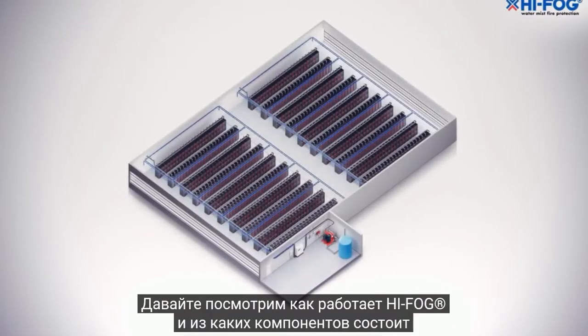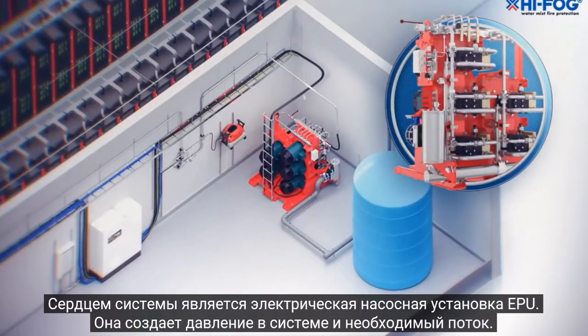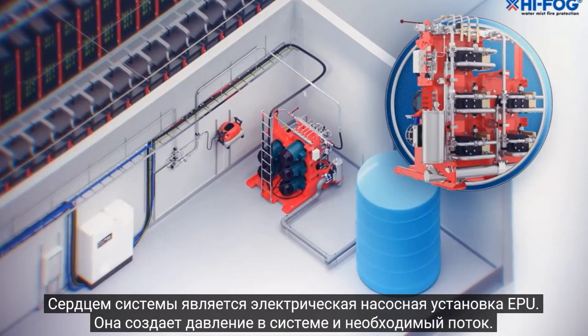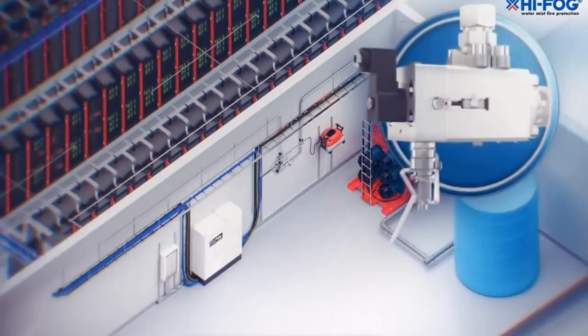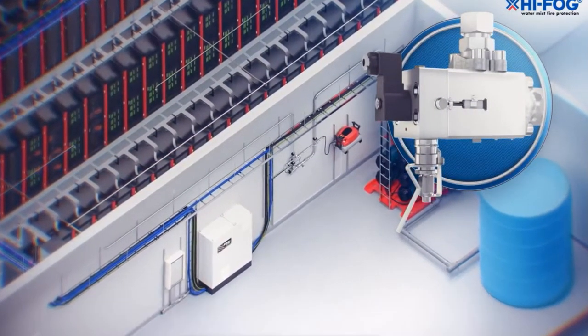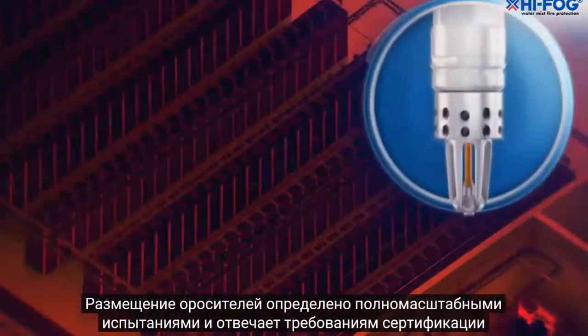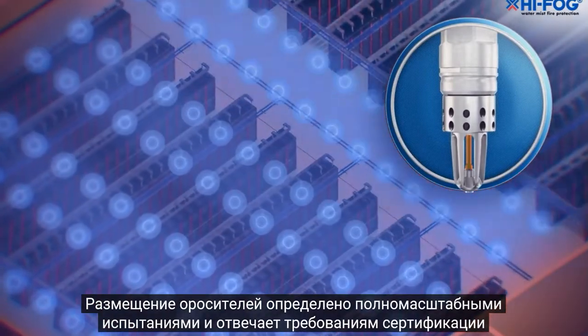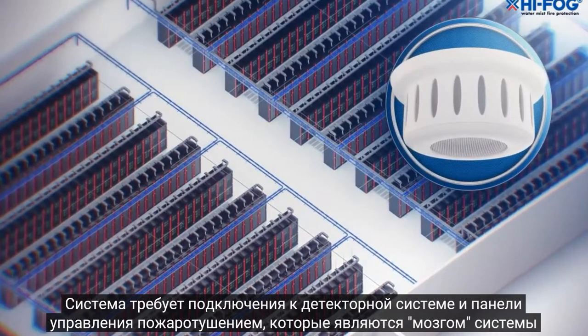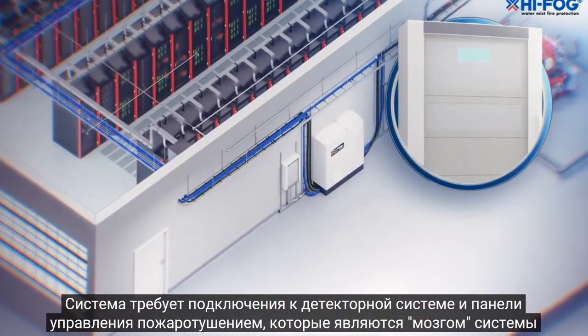Let's take a look at how HI-FOG fire protection works and what components it consists of. The heart of the system is the HI-FOG Electric Pump Unit, which pressurizes the water and provides required flow. Specifically designed valves are designed to prevent a false discharge. Pressurized water is distributed through stainless steel pipes. The layout of the sprinklers is designed to fit the criteria determined by full-scale fire tests and approvals. Other components that the system requires are detectors and a release panel that functions as the brain for the whole system.